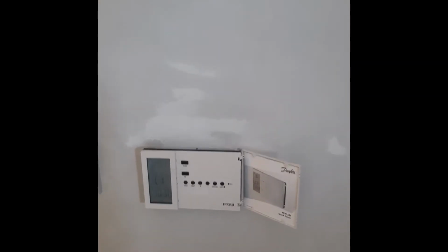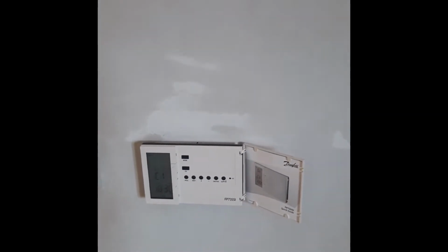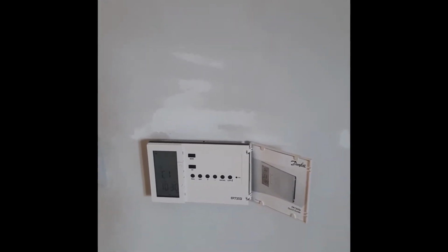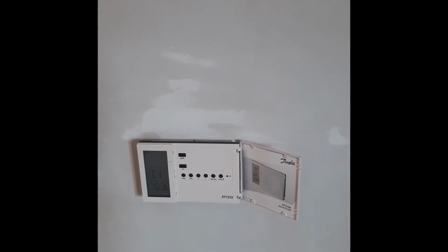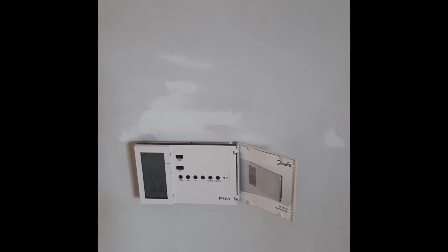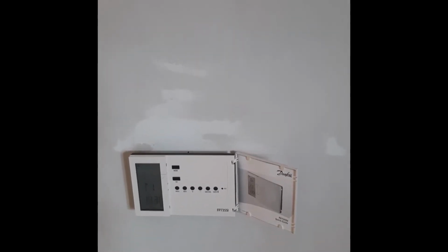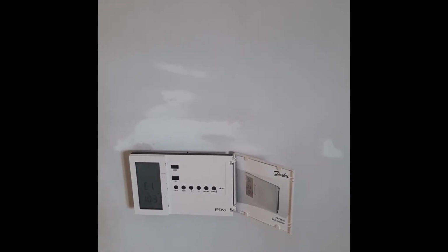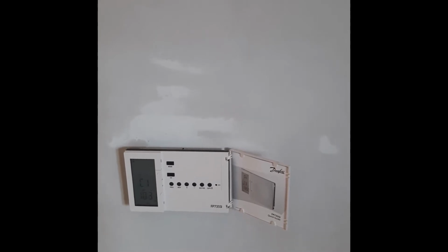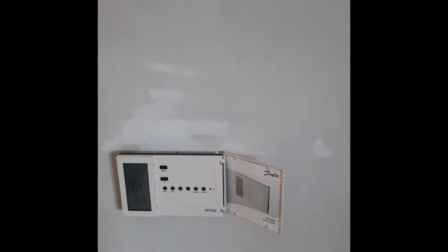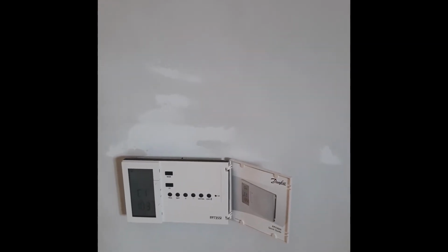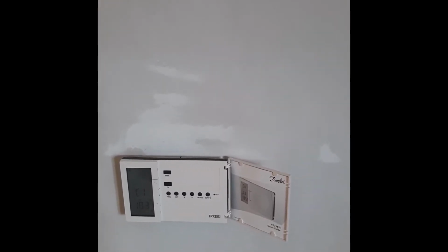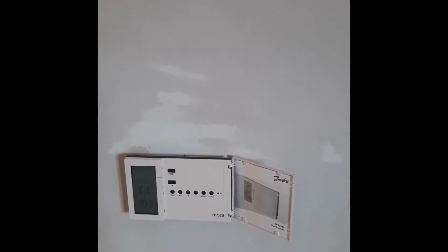This is the time clock. It's 3 channels. Channel 1 is your downstairs heating only. Channel 2 is your upstairs heating only. And channel 3 is your hot water. The channel for downstairs heating is run by this clock, which relates to a thermostat on the wall, which controls the temperature of the downstairs. That thermostat's very important, because if it's 20 degrees in the living room and the stat's at 17, your heating won't come on and you think your heating's faulty. It's not. You've got to turn the temperature up above 20 to get the heating to come on, but we'll go through every stat later.